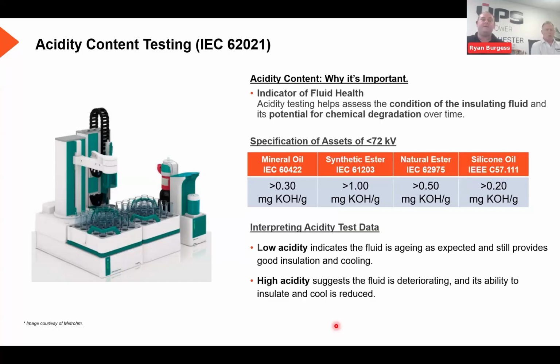Go on, Andrew. Yeah, so the consequences of having high acidity means that it has the potential to form sludge, and the sludge collects on the windings and other parts of the transformer and reduces its insulating properties.